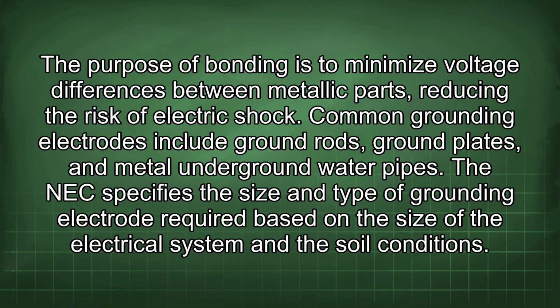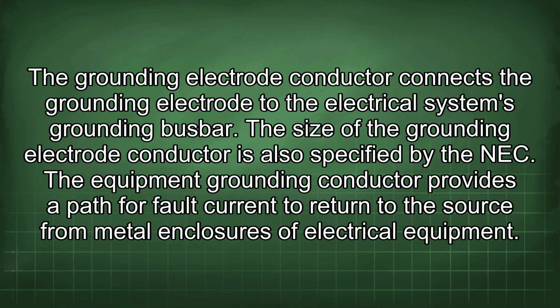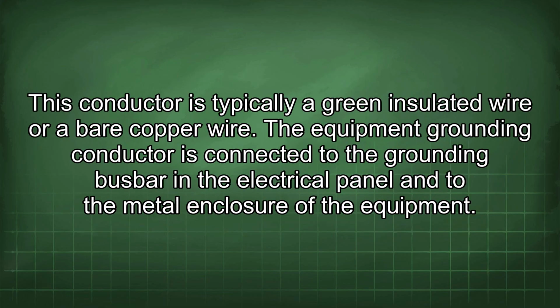The NEC specifies the size and type of grounding electrode required based on the size of the electrical system and the soil conditions. The grounding electrode conductor connects the grounding electrode to the electrical system's grounding busbar. The size of the grounding electrode conductor is also specified by the NEC. The equipment grounding conductor provides a path for fault current to return to the source from metal enclosures of electrical equipment. This conductor is typically a green insulated wire or a bare copper wire. The equipment grounding conductor is connected to the grounding busbar in the electrical panel and to the metal enclosure of the equipment.